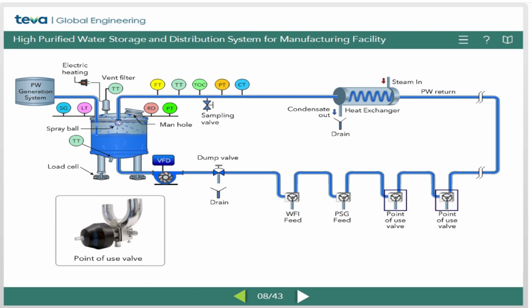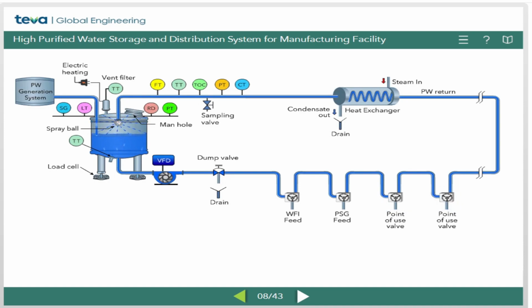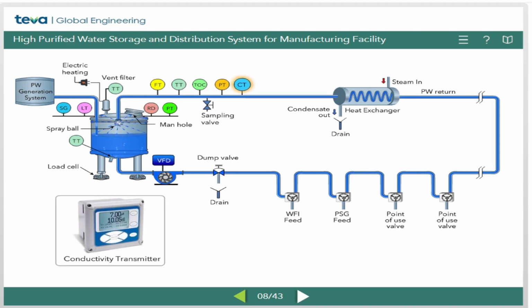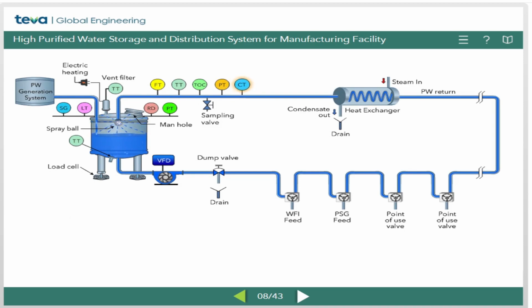Point-of-use valves should be zero dead leg or T-pattern block valve. These valves can be manual or automatic. However, the valves connected to the process equipment or vessels should be automatic with a built-in sampling valve. A cluster of instruments are installed in the return line of the distribution loop, such as conductivity transmitter to ensure the conductivity of PW is within the acceptable limits.